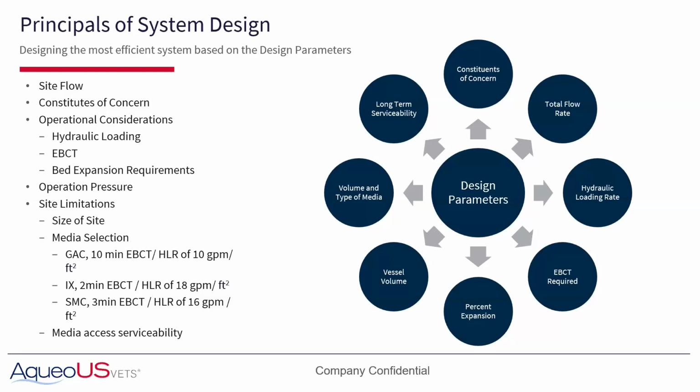The ion exchange resin and the specialty medias are down around 2 to 3 minutes. So these systems will be much smaller with these other media compared to the activated carbon. You also need to be able to access the media. Again, they're going to be changed out periodically.